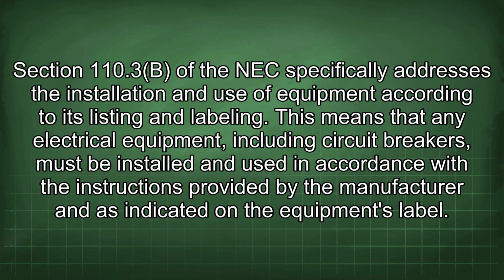Section 110.3(B) of the NEC specifically addresses the installation and use of equipment according to its listing and labeling. This means that any electrical equipment, including circuit breakers, must be installed and used in accordance with the instructions provided by the manufacturer and as indicated on the equipment's label.